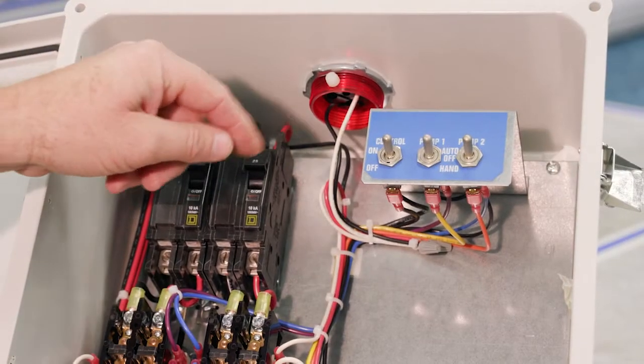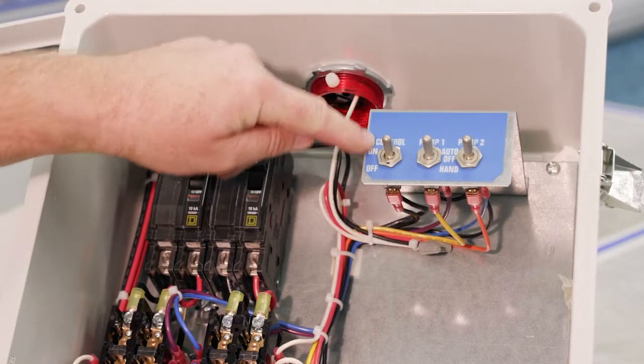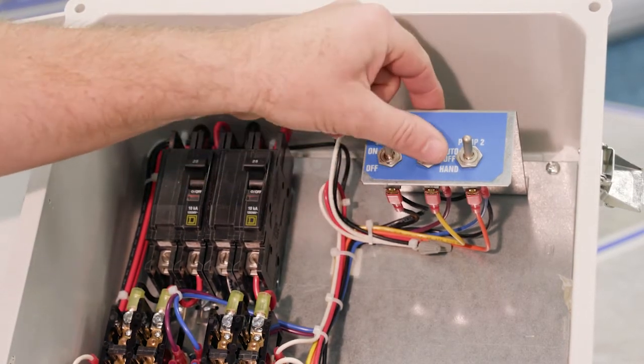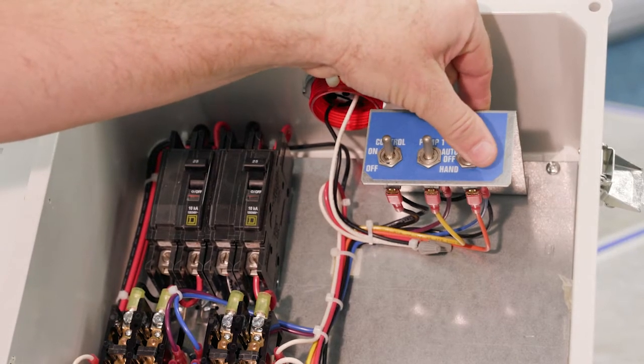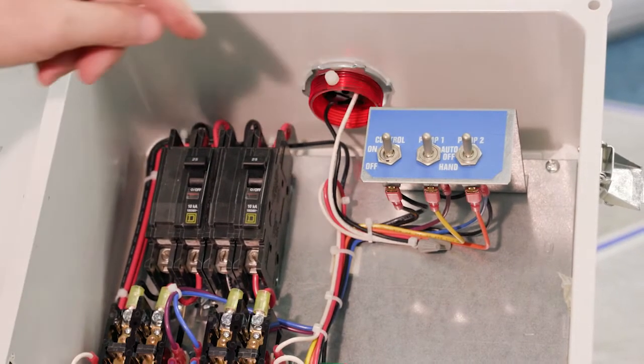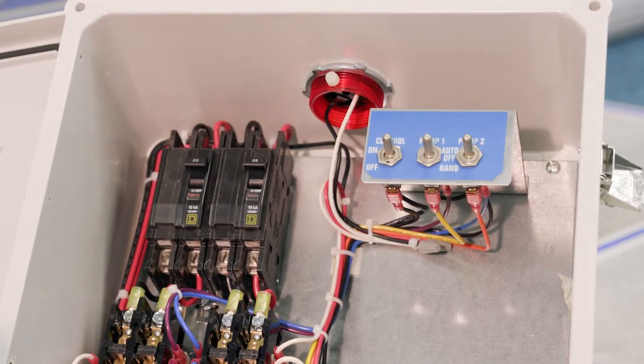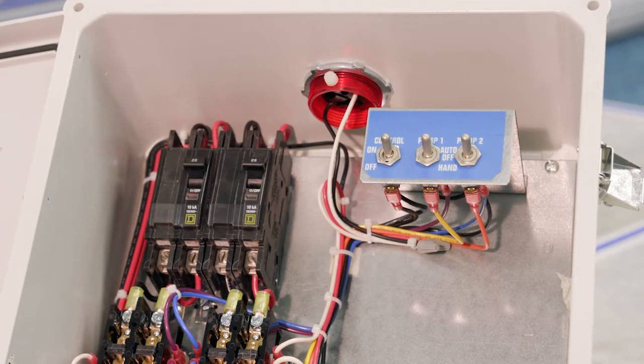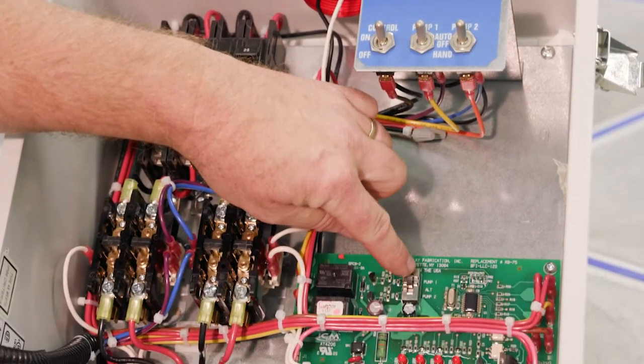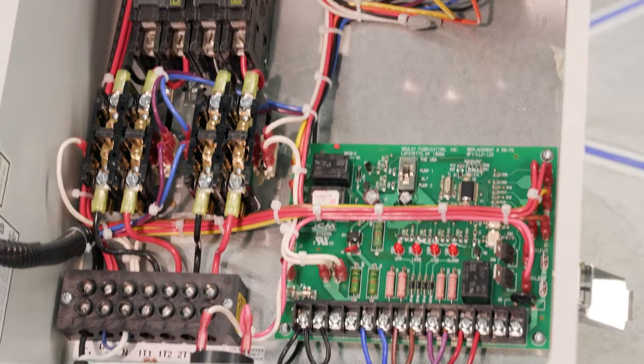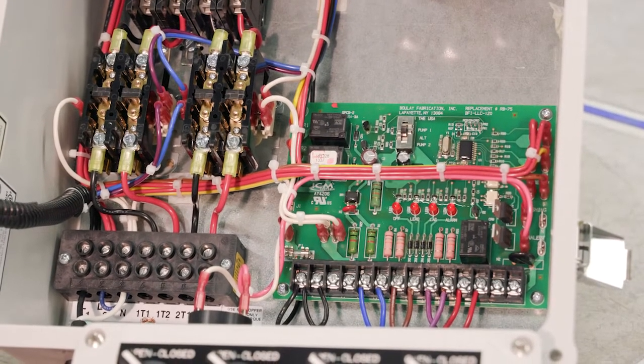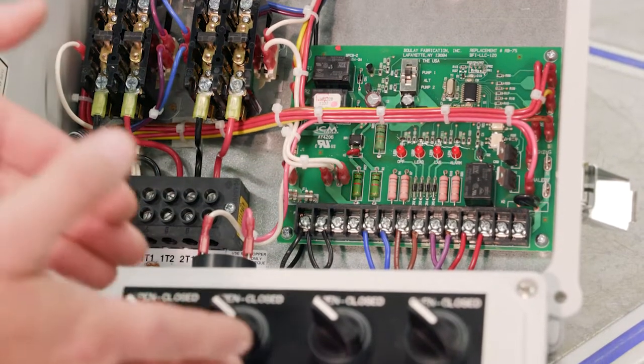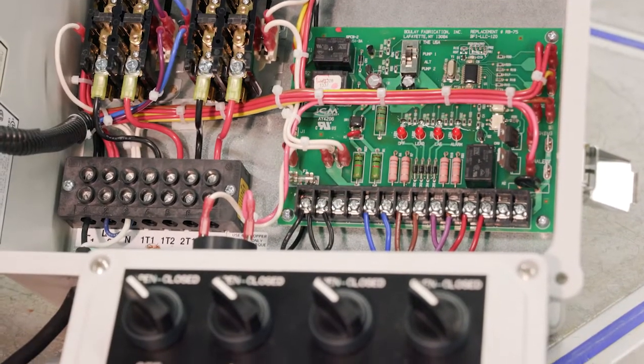One thing we have to do is we've got to make sure the control switch is on. And also our HOA switches are set to auto. So hand off auto. Auto basically means that it's going to automatically work based on your float switches. So we've got those set properly. The alternator, which is right here, make sure that's in the middle, set to alternation. So now what we're going to do is we've got power applied, the power is turned on, and then we're going to simulate those float switches.